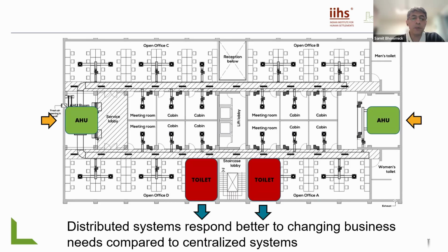In general, from my experience, I found that distributed systems respond better. So if you have the toilet extract fans on the terrace of a taller building with multiple floors, some floors might not be occupied, but you'd still run the extract fans because all of them are connected to the same extraction unit. Having them floor-wise lets you switch off floors in case of a multi-tenanted building, where tenants may or may not be available on a certain floor. The system design in general should let you respond to the business need.